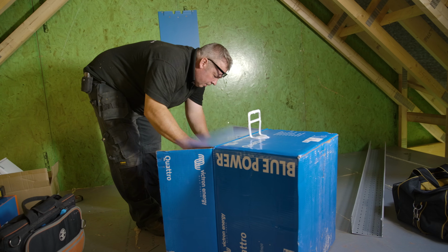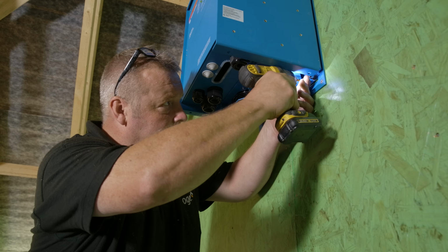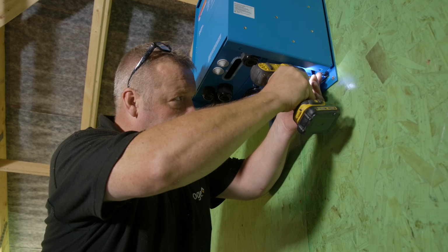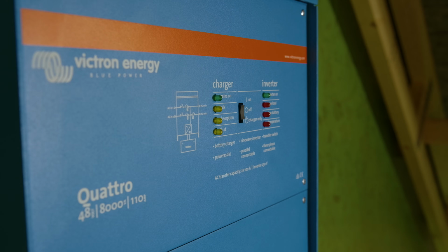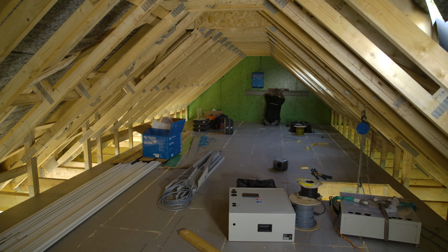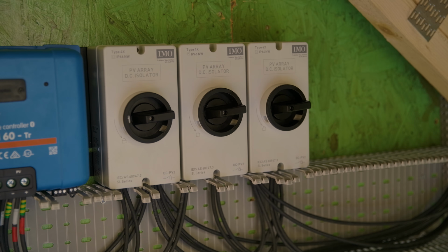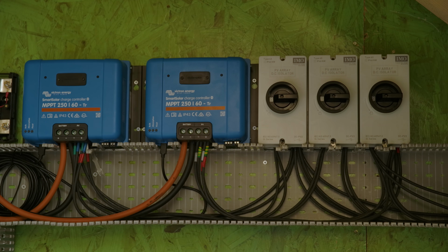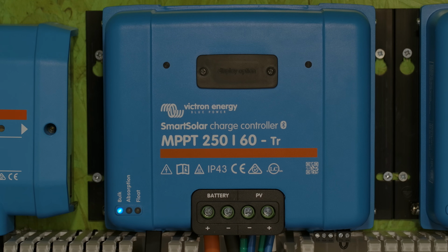The first piece of equipment to be mounted onto the gable end wall is a 48 volt 8 kVA Quattro inverter charger. All the cables have been fed in from the solar panels on the roof and will first go through 3 switches and then to 2 Victron Energy MPPT 250/60 smart solar charge controllers.